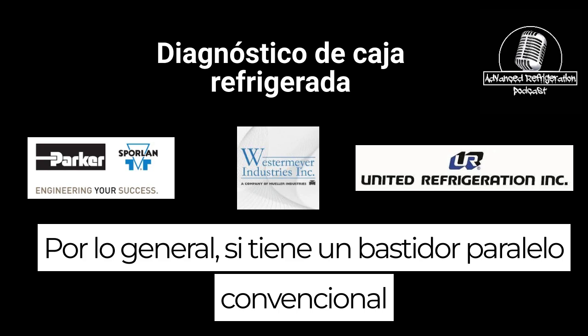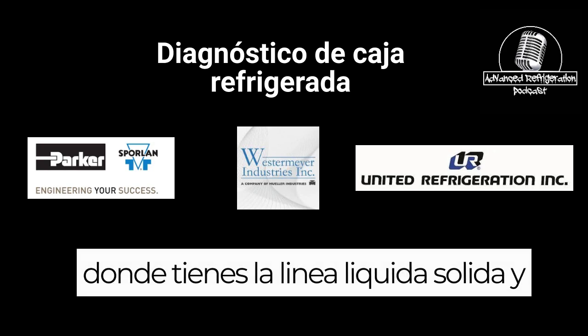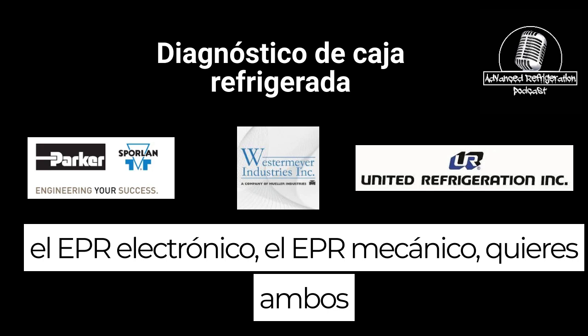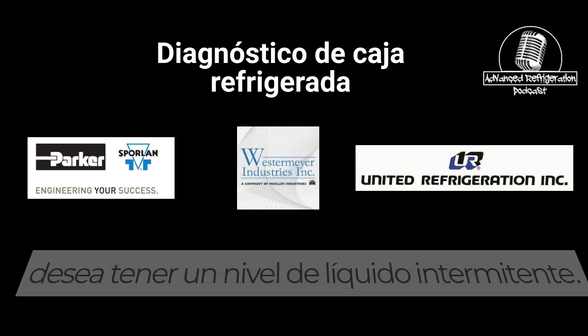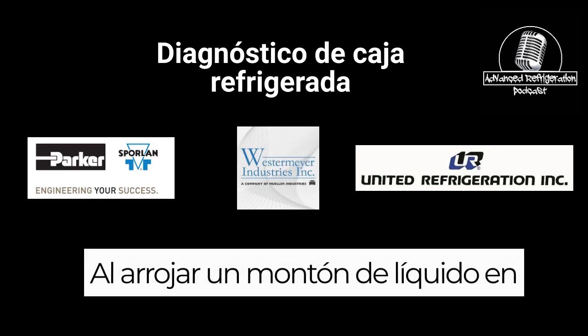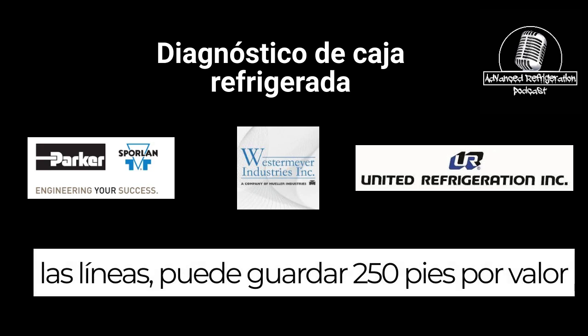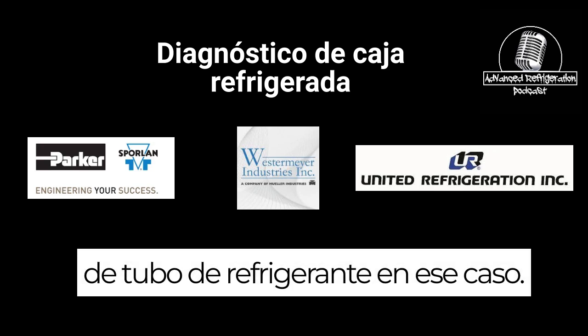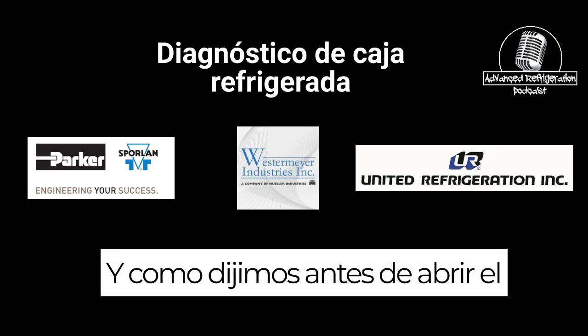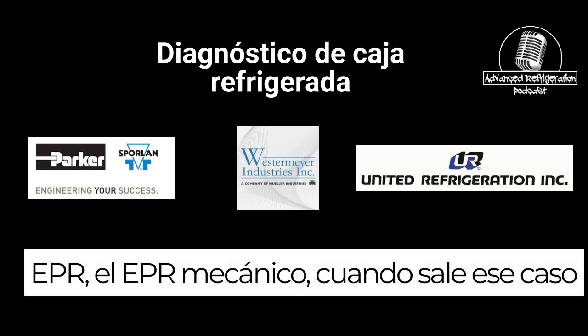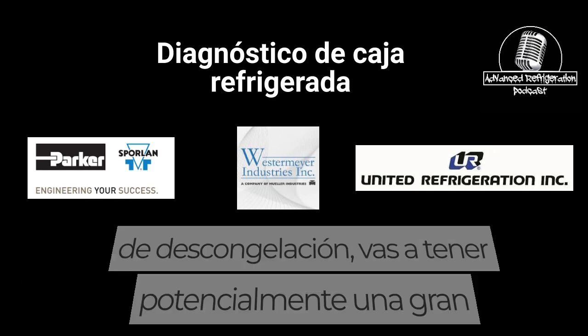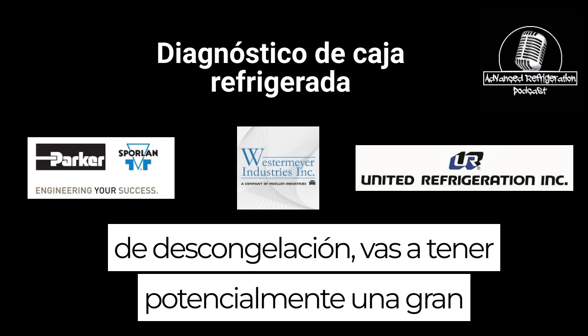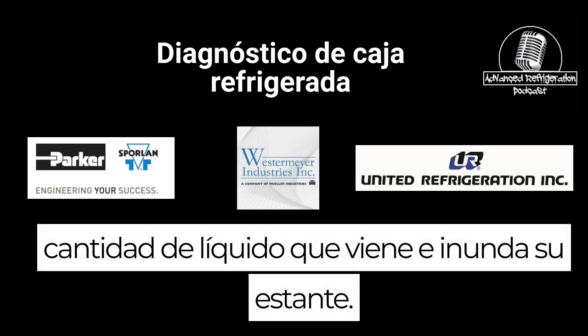Usually, if you have a conventional parallel rack where you have the liquid line solenoid and the electronic EPR or mechanical EPR, you want both those valves to shut off because you don't want to have intermittent liquid level, throwing a whole bunch of liquid in the lines. You might store 250 feet worth of pipe of refrigerant out into that case. And so, like we said before, with opening up the mechanical EPR, when that case comes out of defrost, you're going to have potentially a large quantity of liquid coming and flooding out your rack.